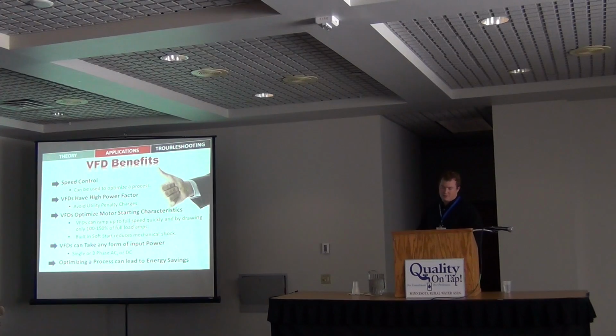They optimize motor starting characteristics. We can ramp up to full speed quickly by drawing 100 to 150% full load amps. If we're starting a motor across the line, we're over 200%. And if we're starting a really big motor across the line, when we have that high amp draw, what happens is the utility can't keep that voltage up. Your voltage will drop on your system, and you might have your lights go out, you might have problems on your system that way starting across the line. So a VFD and a soft start eliminate that.